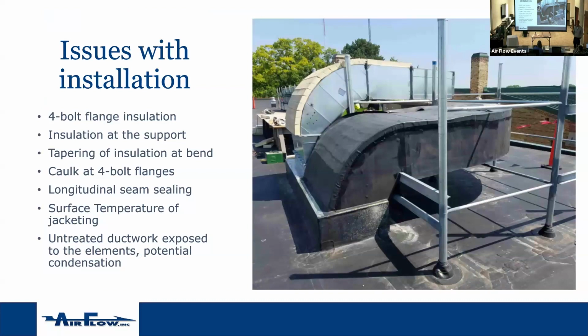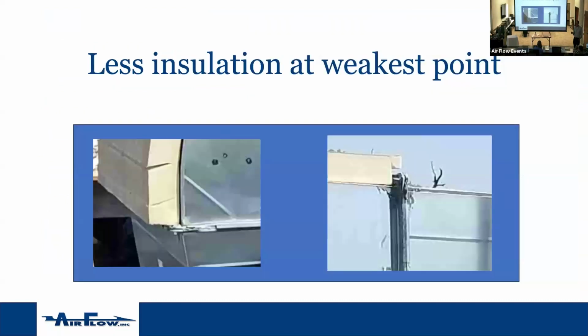We have some insulation challenges. We've got a lot of caulking. We've got some surface temperature stuff. Let's go through those one at a time. So if we're going to wrap this ductwork with cladding, and then we've got that flange, we kind of need to chop off our insulation where the 4-bolt flanges are. Now, is that the biggest deal in the world? Probably not. It's just a small detail, but it's a detail.